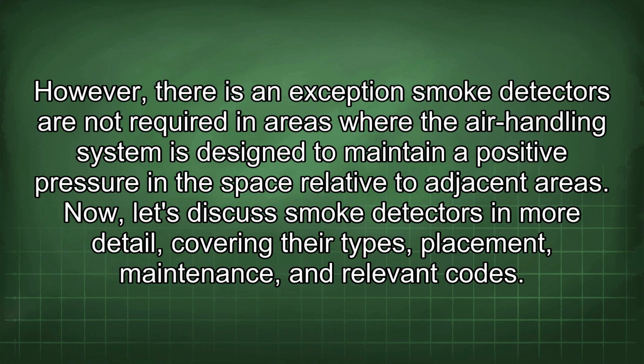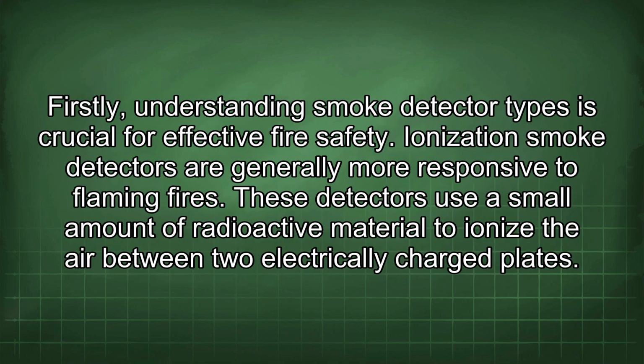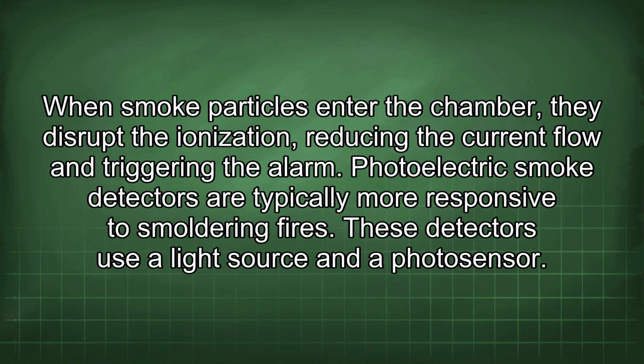Now let's discuss smoke detectors in more detail, covering their types, placement, maintenance, and relevant codes. Firstly, understanding smoke detector types is crucial for effective fire safety. Ionization smoke detectors are generally more responsive to flaming fires. These detectors use a small amount of radioactive material to ionize the air between two electrically charged plates. When smoke particles enter the chamber, they disrupt the ionization, reducing the current flow and triggering the alarm.